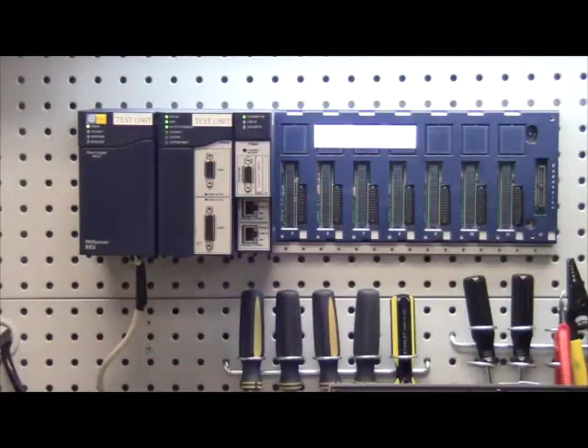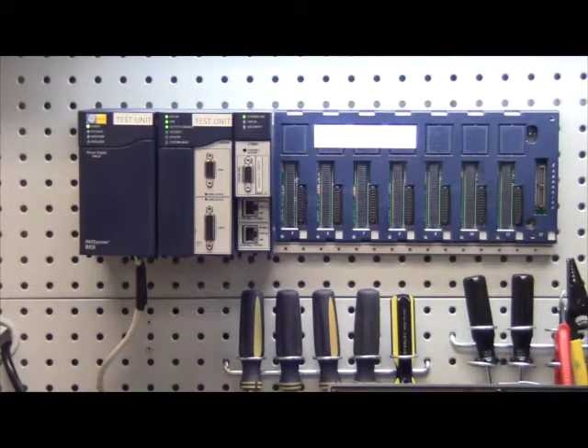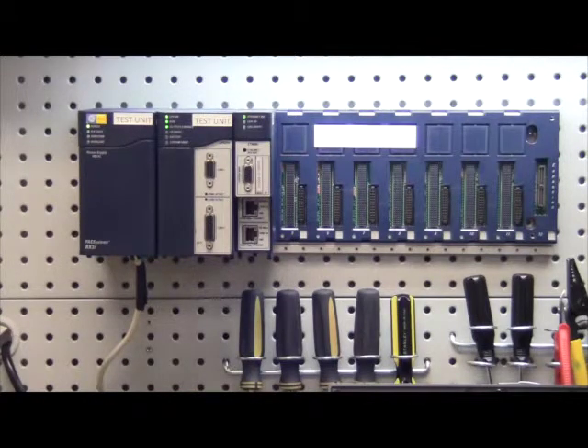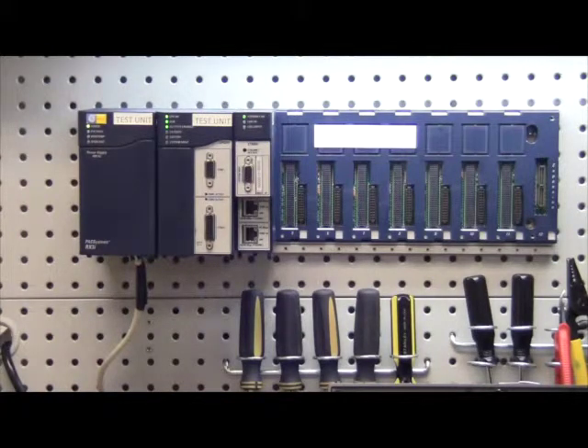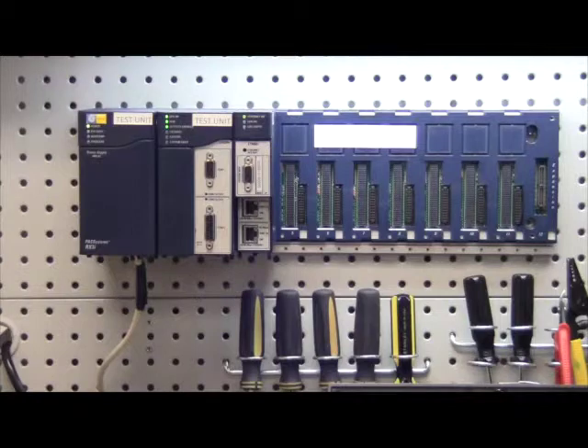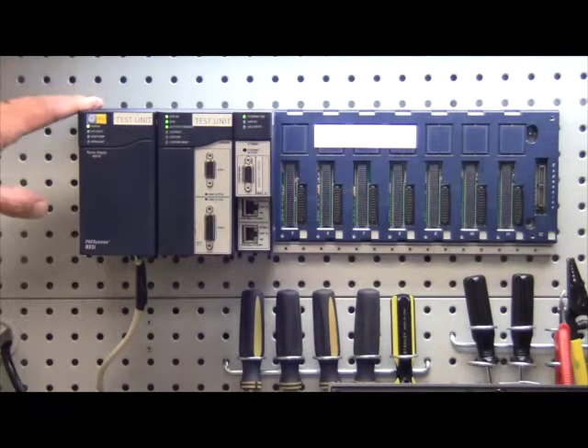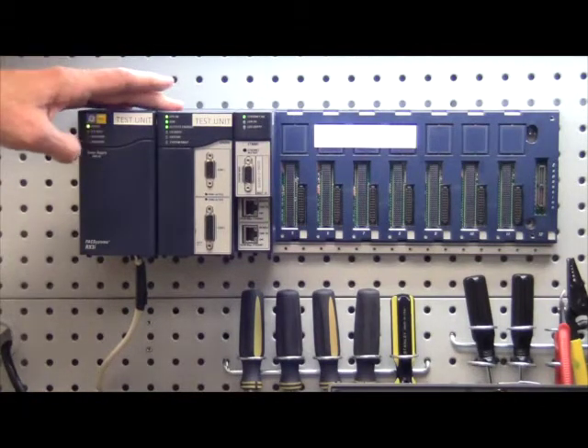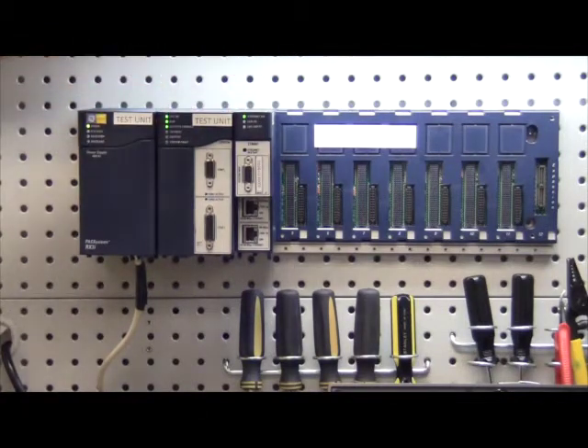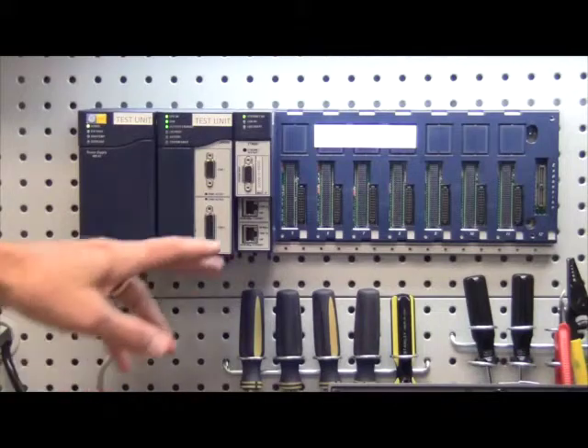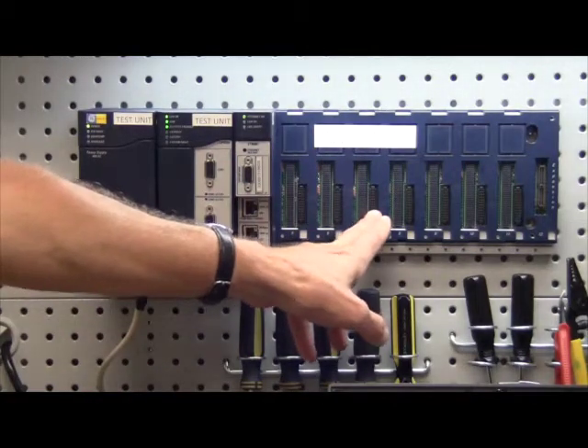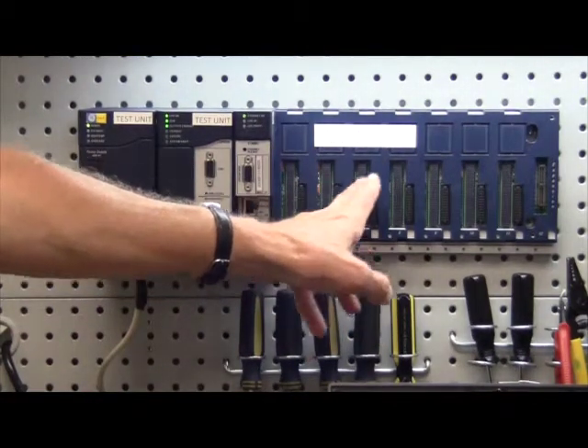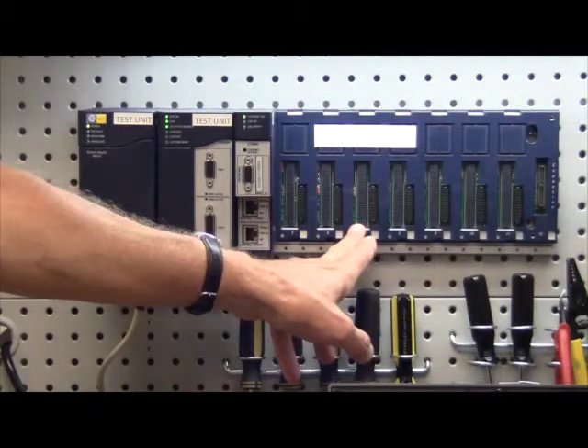The RX-3i processor is the up-and-coming PLC or PAC system as GE calls it now, basically replacing almost all formerly sold systems because of its power and compact nature. The RX-3i includes a power supply, a CPU, an ethernet module and multiple I/O. What you will note in the back plane is it allows the old 90-30 I/O to be plugged in as well as the new high-speed RX-3i I/O.